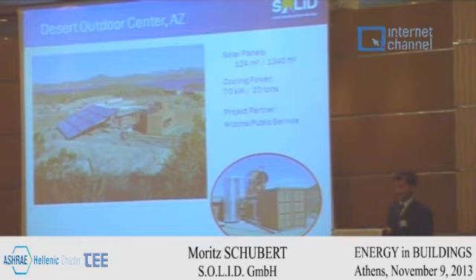It all went well when we started it five years ago, but in the second season, since they have around nine months of cooling demand and three of heating, after the heating demand we wanted to start the chiller again. They called us in Austria and said there's a problem, they couldn't start the cooling system. We looked at our remote operating system and saw there was an issue with the cooling tower. We told them to check it, and they found a family of birds breeding inside, with a nice place to stay. We had to remove those birds, and from then on the solar cooling system ran perfectly again.